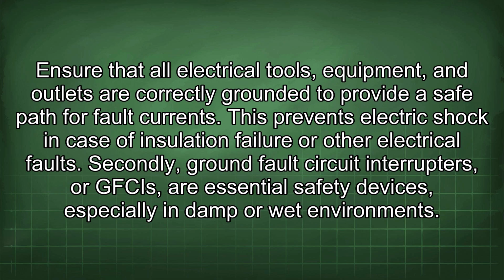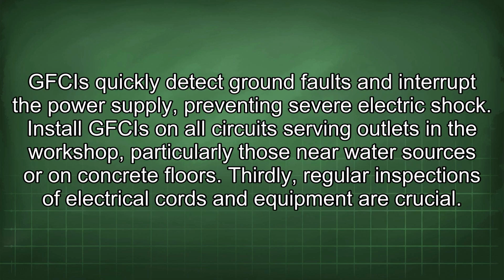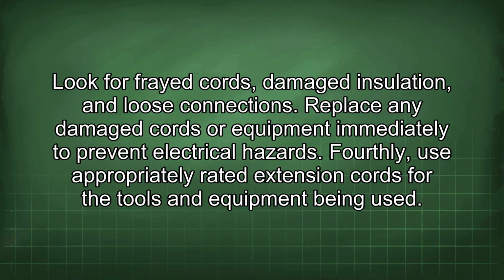Secondly, ground fault circuit interrupters, or GFCIs, are essential safety devices, especially in damp or wet environments. GFCIs quickly detect ground faults and interrupt the power supply, preventing severe electric shock. Install GFCIs on all circuits serving outlets in the workshop, particularly those near water sources or on concrete floors. Thirdly, regular inspections of electrical cords and equipment are crucial. Look for frayed cords, damaged insulation, and loose connections. Replace any damaged cords or equipment immediately to prevent electrical hazards.